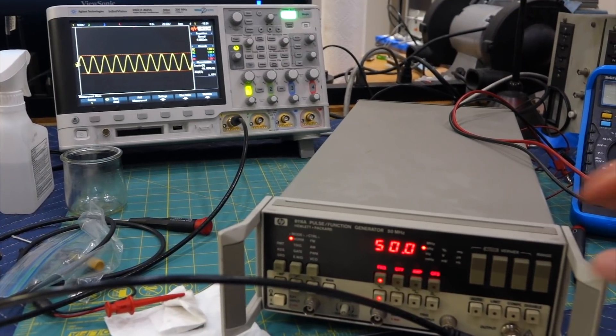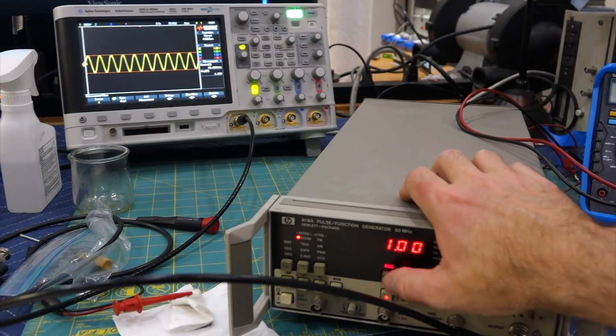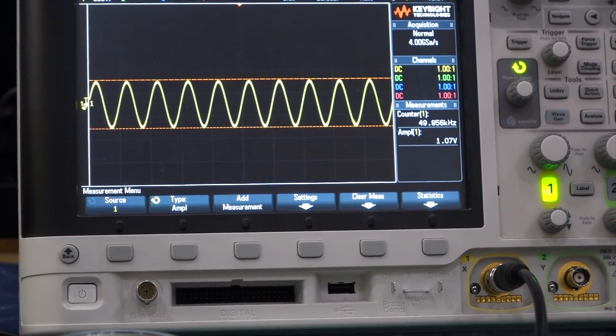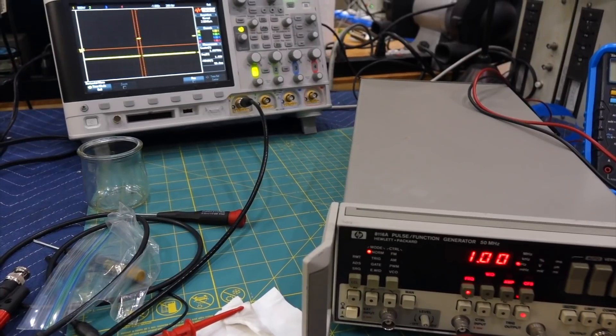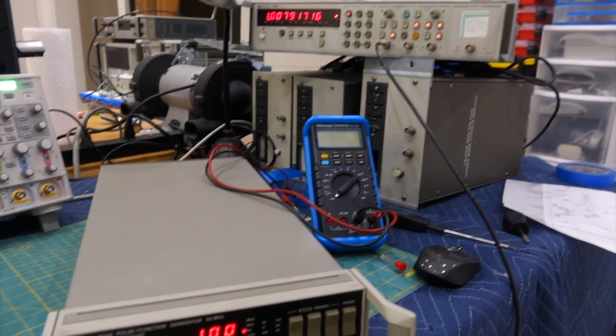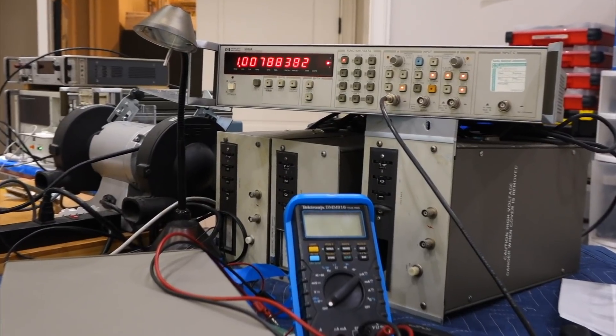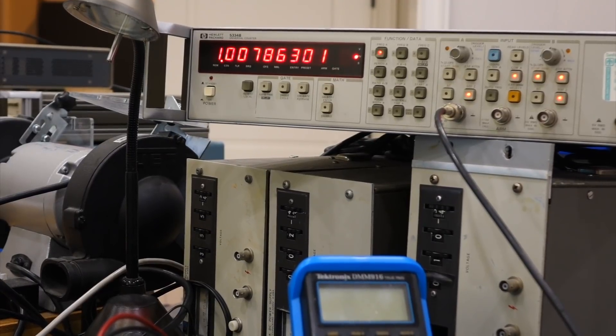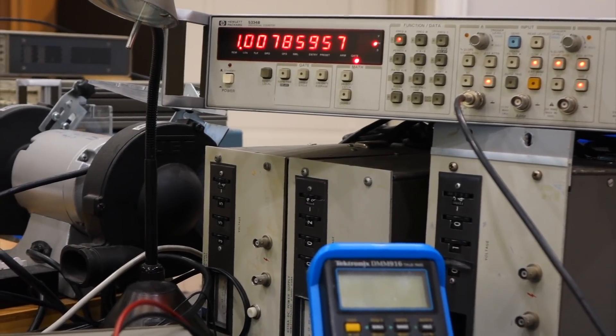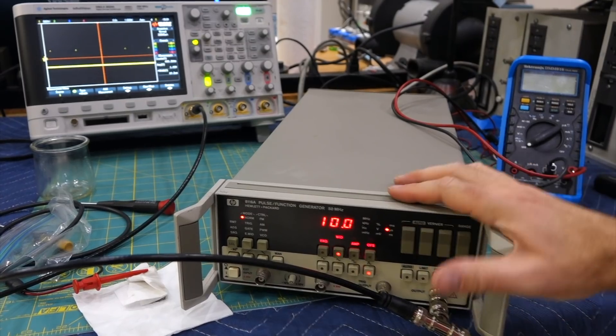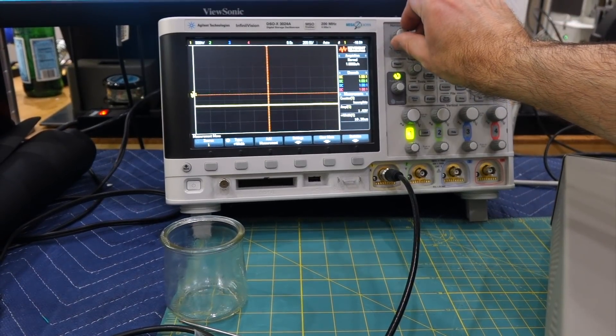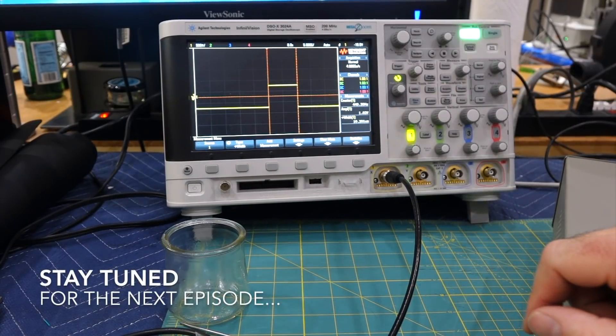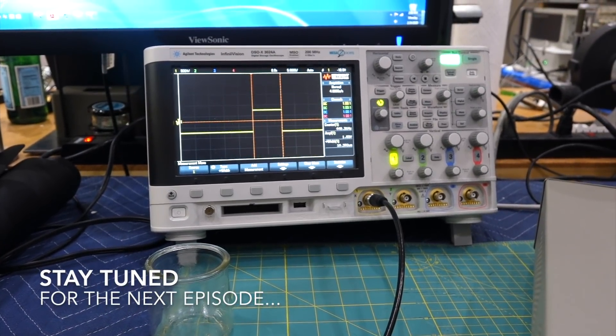And here's the results. This used to be all over the place. Now I get 49.956 kilohertz and 1.06 volt. And then if I ask it for a one second pulse, it tells you 1.00. And it actually now shows, it just gives you what it can give you. It gives you two decimals, 1.00. And it's not a quartz based instrument, it's just completely analog. So you can't expect that much precision for it, which actually I didn't know. If I ask it for a 10 microsecond pulse, it's hopefully going to give me a 10.20 microsecond pulse. Well done, HP 8116!